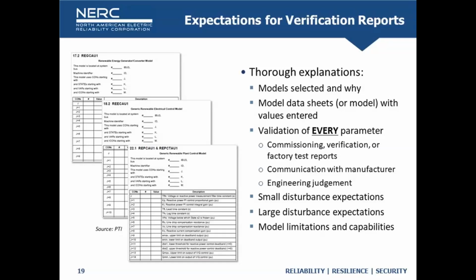We can then look at the plant level controller model, and there goes 15% of the other models. Then we can look at, is the plant using reactive current injection or momentary cessation, and what's their K factor, and how fast does their active power recover after the fault? And there goes another 30% of the parameters. I've only got a handful left that I could verify. And I haven't compared squiggle against squiggle yet. I've done something, in my opinion, that's much more valuable in terms of comparing what's out there in the field versus what my model thinks it should be.